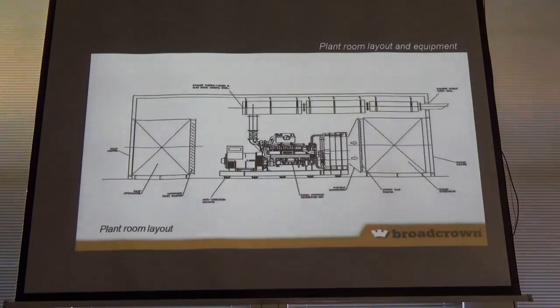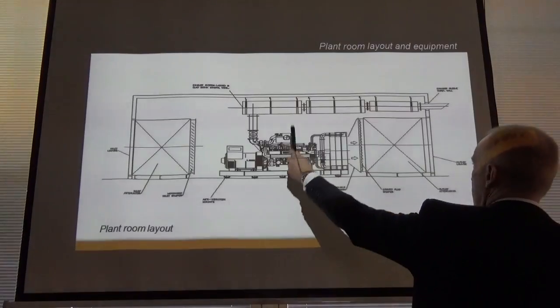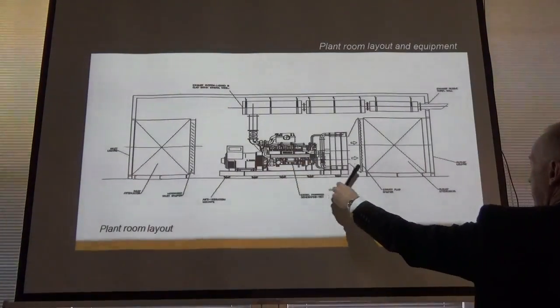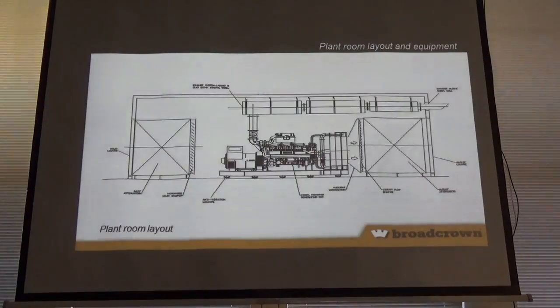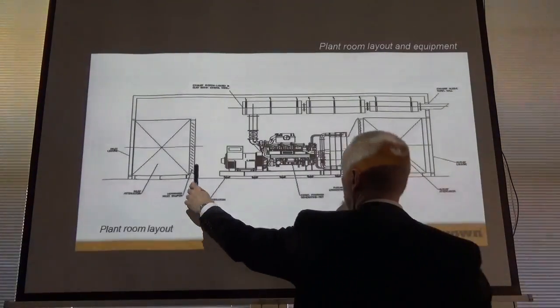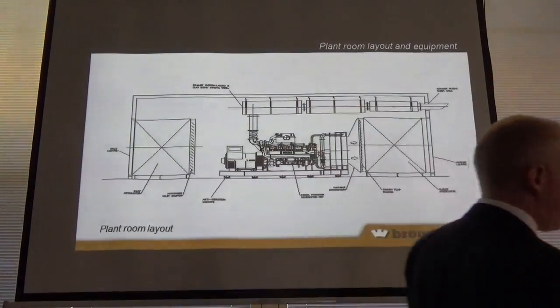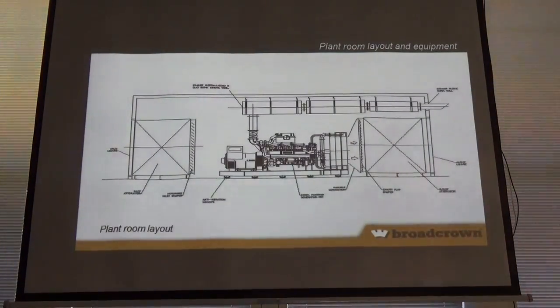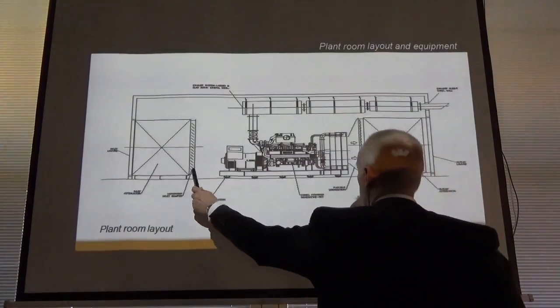When the set's up and running and up to return temperatures of 80, 85 degrees C to the engine block itself, it's a nice running temperature. So its load acceptance is actually going to be better. Load acceptance and recovery, because it's fully up to temperature. All right. So you get quite a bit of radiant heat from there, which keeps it nice and warm in the space. So if you've got a slight breeze blowing through, the last thing you want is the jacket heaters on all the while. So ideally what you'll do is you'll have motorised inlet, maybe gravity discharge louvers that will basically enclose that room. So it's easy to work in, more controlled environment, and your jacket heater's not working as much as well. These are spring open motor close.